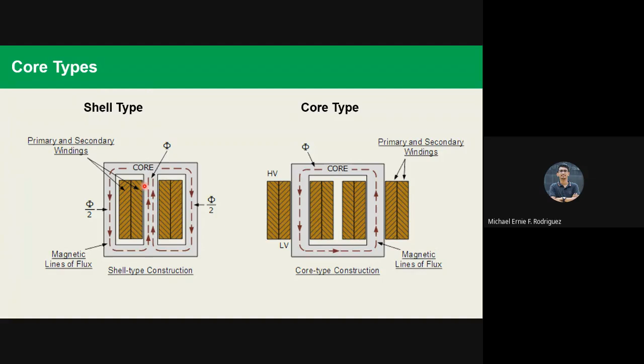Ibig sabihin, kadalasan pag ganito, pag shell type, three-phase units, mga 3-phase transformers ito, hindi yung core type. Sa core type, kung mapansin nyo, yung windings ay nasusurround sa steel core. Ang resulta nito, it results in a more compact, smaller unit. Hence, they are generally more suitable for the sizes of transformers associated with overhead and radial primary distribution systems. Ito yung ginagamit natin for sa mga overhead natin. Kadalasan, these are almost always single phase units.